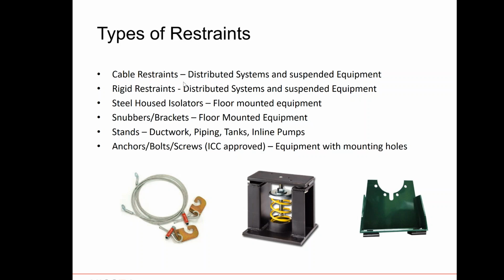And these could be cable restraints that are usually used for distributed systems and suspended equipment, rigid restraints, which would be brackets with a piece of strut or angle in between that would work as a two-way restraint for distributed systems and suspended equipment. Steel-housed isolators, so an isolator like you see here in the middle that has a housing around it. The isolator allows small movement for vibration isolation, but under any event, the housing strength will kick in and basically stop the equipment from moving. Snubbers and brackets that maybe are put around a piece of an air handling unit or a piece of equipment to stop it from moving.